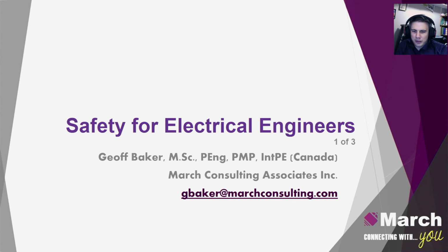The first thing I did was bolt to the end of the electrical room so I was outside the danger, and then I yelled down to him asking if he was sure he should be doing this right now. He took a minute and realized, oh yeah, this equipment is all live, I don't even know if I'm authorized to open this. He went and talked to his manager and found out that if he had opened that door, it would have shut down the entire site, because it had a safety interlock that prevents people from getting inside with that much energy potential unless the power is shut off. He probably would have gotten fired if he'd done it. Thankfully he didn't, and nobody got hurt.